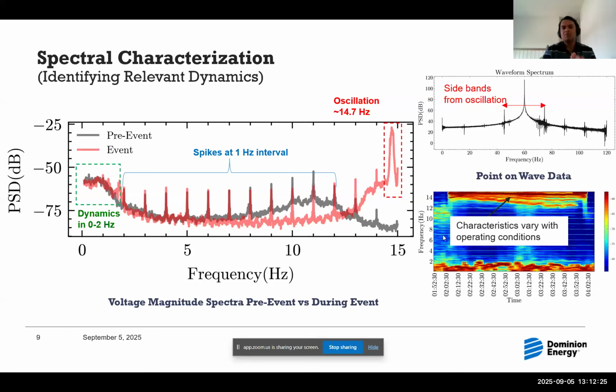Starting with the spectral characterization: the oscillations were first, or mainly, seen in voltage magnitude, so I picked up voltage magnitude from that region, starting with the data center bus. I don't know if the source is there, but the data center substation definitely saw the oscillation. At peak voltage magnitude, we pick up a pre-event ambient period and the during-event period to contrast the spectral characteristics.